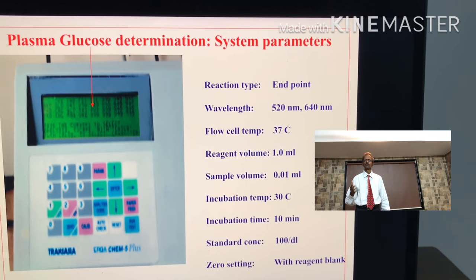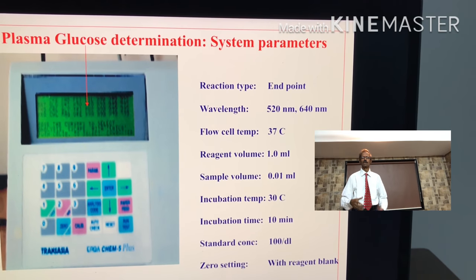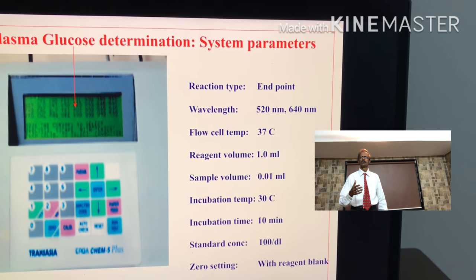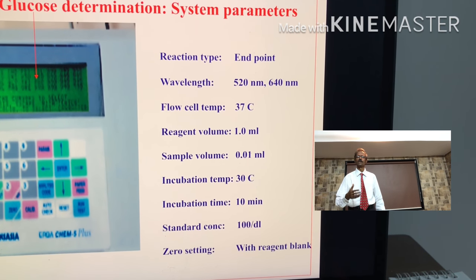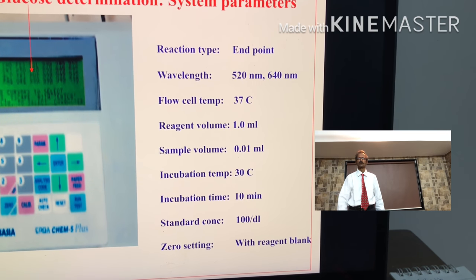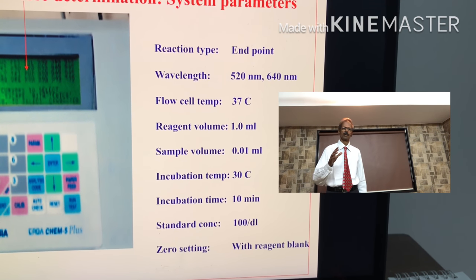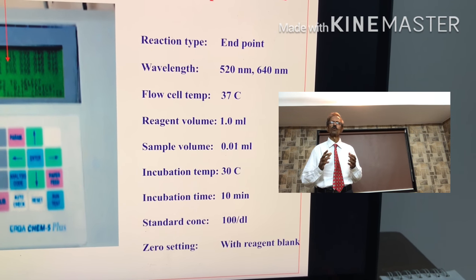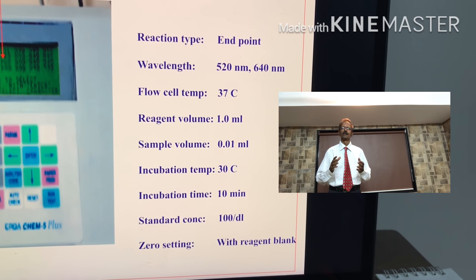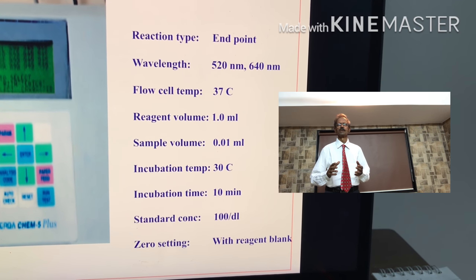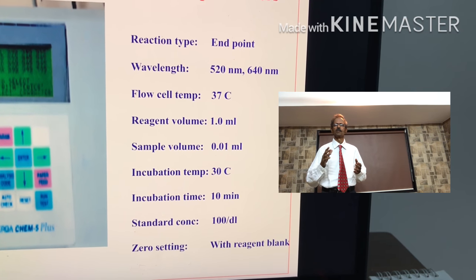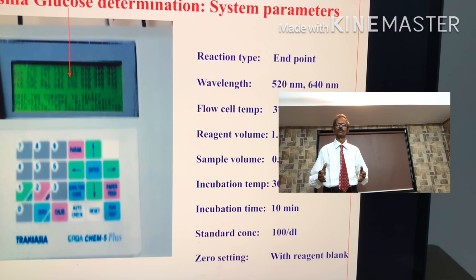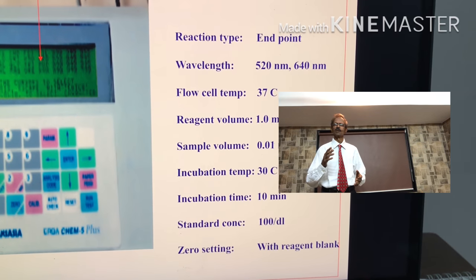Let us take another example of plasma glucose determination. The kit literature will give system parameters like this: reaction type — end point reaction method; wavelength; flow cell temperature; reagent volume; sample volume; incubation temperature; incubation time; standard concentration; and how to set your photometer or analyzer for zero setting — and this is with reagent blank.